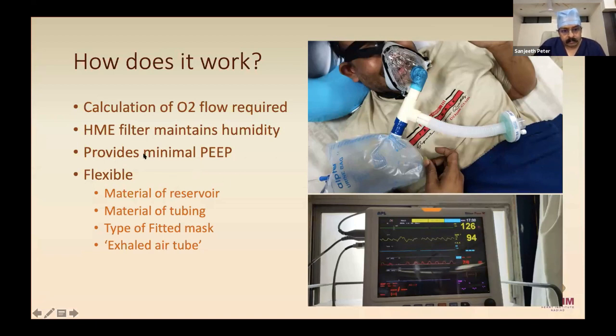The HME filter at the end of this, if you can see there, actually maintains the humidity. We had a bit of a problem initially that even the oxygen we were providing to this entire circuit was humidified oxygen, the one that goes through this oxygen bubble trap. And then we found that a lot of humidity was developing within the circuit.